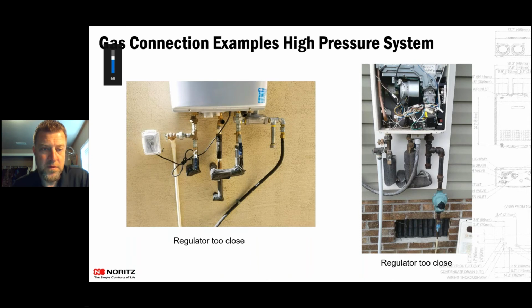There are some who claim that if the gas line is sized a little bit under what it should be, or what's indicated in the code, the unit itself will pull the gas through at a higher rate. Is that true or not? Yeah, so we do have units with a negative pressure gas valve. A lot of manufacturers are starting to use those. We have a competitor that says their negative pressure gas valve will pull 100 feet through a half-inch line and give you 199,000 BTUs.